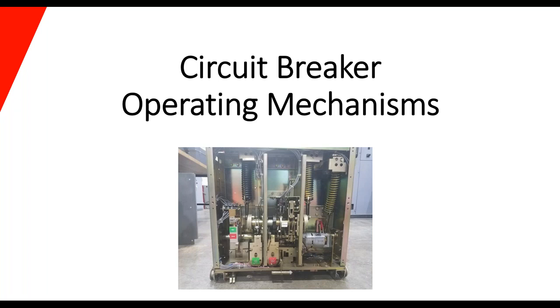When talking about the circuit breaker operating mechanism, you have to understand that to be good at it you need to know how the breaker works both mechanically and electrically. Without knowing how it functions mechanically, there's really no way you'll be able to interpret a line diagram or schematic of a circuit breaker. Mechanically, if the breaker has limit switches, auxiliary contacts, or a motor, you want to know where those are, what they do, when they do it, why they do it, and what goes wrong when they don't — just like you would a garage door opener.